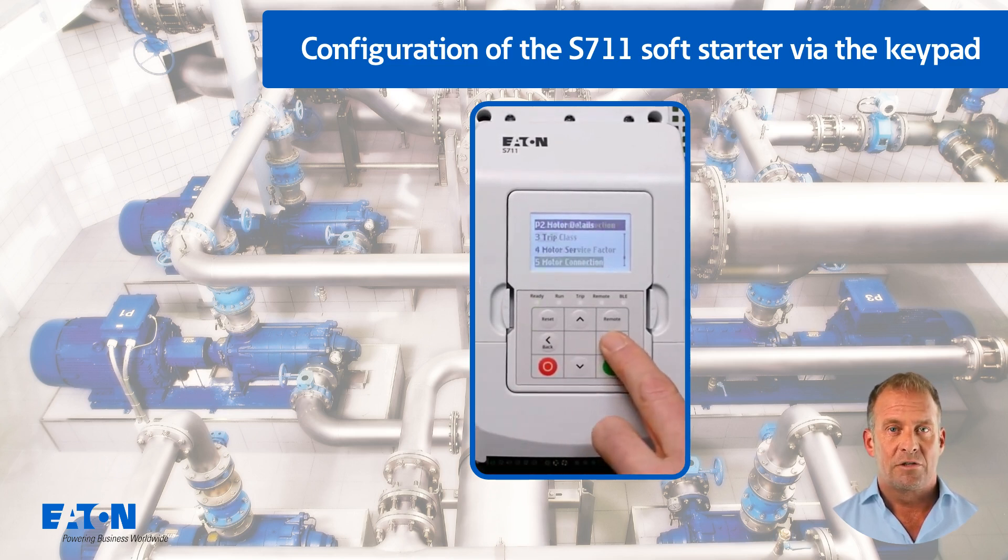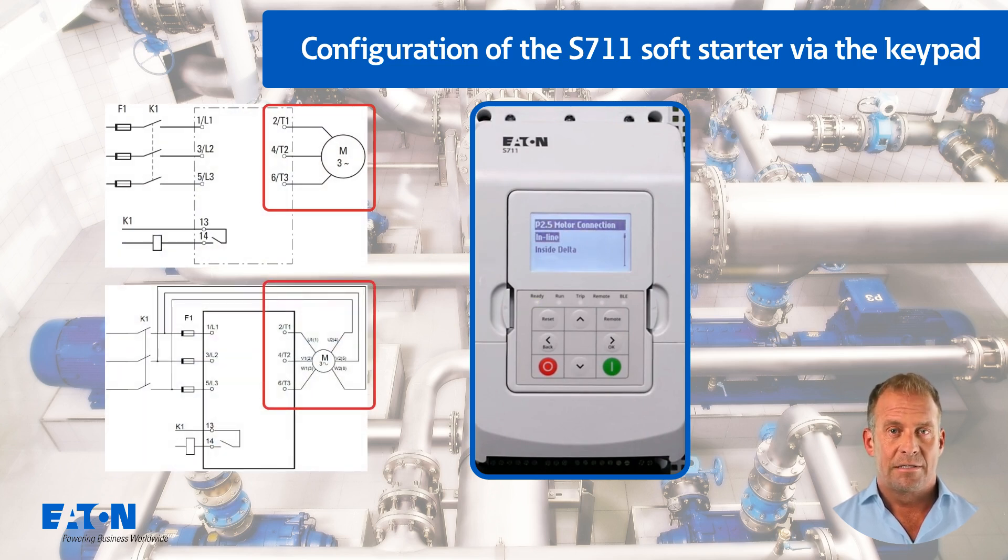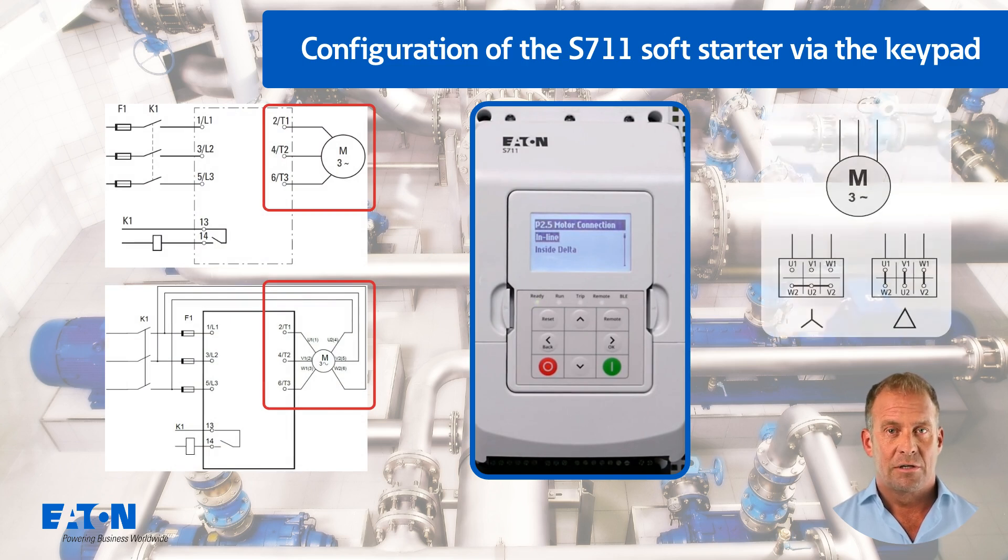P2.5 is used to set whether the connection between the device and motor is inline (three lines to the motor) or inside delta (six lines to the motor). The inside delta configuration must not be used if the motor itself is connected in star.